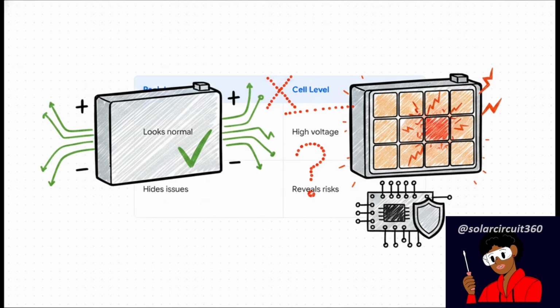If you zoom into the cell level, you might find that a single rogue cell is secretly pushing right up against a dangerous thermal event, like severe overvoltage. The BMS is there to protect against this by strictly enforcing limits on every single cell, not just the whole pack. Always follow your specific manufacturer's cell-level voltage limits.